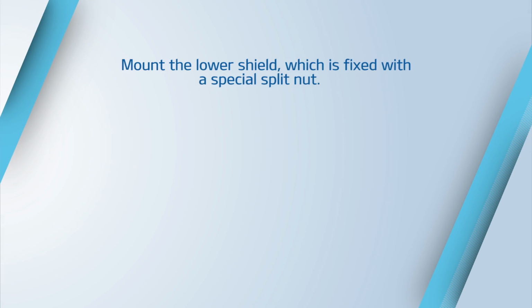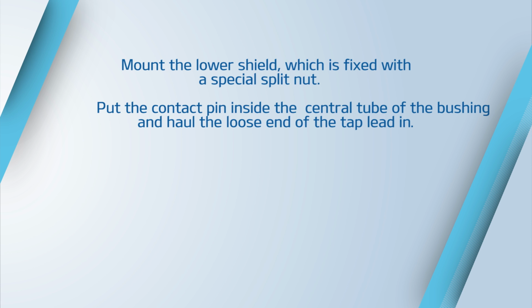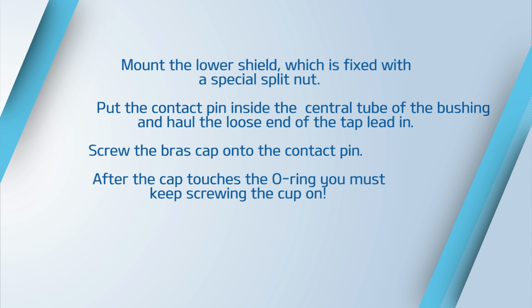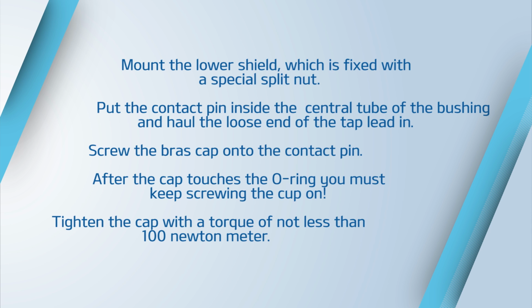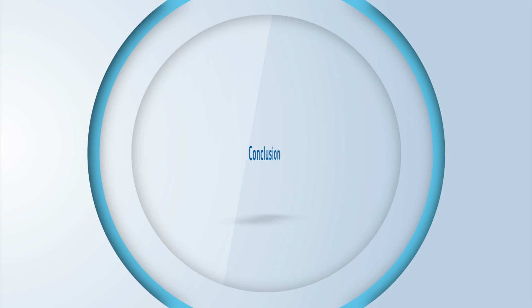Mount the lower shield, which is fixed with a special split nut. Put the contact pin inside the central tube of the bushing and hold the loose end of the tap lead in. Screw the brass cap onto the contact pin. After the cap touches the O-ring, you must keep screwing the cap on. Tighten the cap with a torque key of not less than 100 Nm. Set the contact terminal on the contact pin.